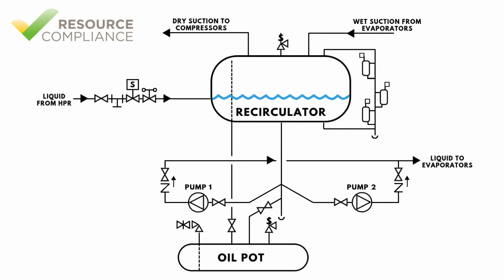Cavitation is a phenomenon that occurs when the pressure of a liquid drops below its vapor pressure, causing the liquid to form vapor bubbles. These bubbles collapse violently when they move into higher pressure zones, leading to damage, noise, and reduced efficiency in refrigeration pumps. To protect against this, the recirculator will also have a low level or cavitation cutout.